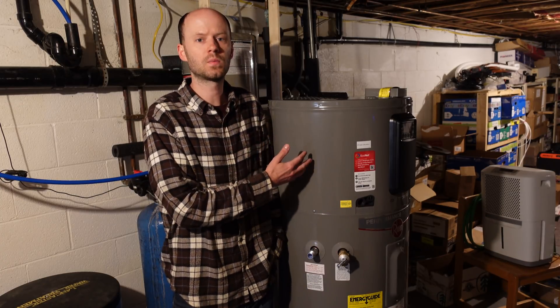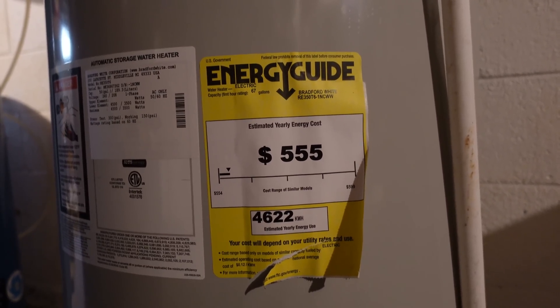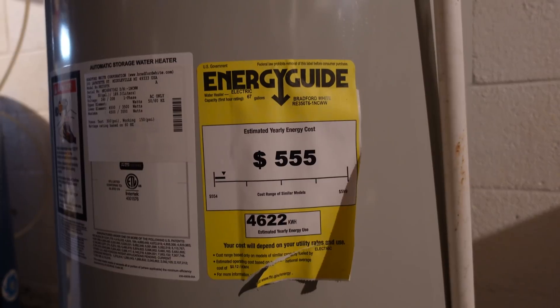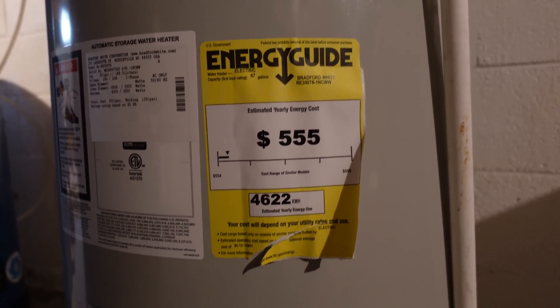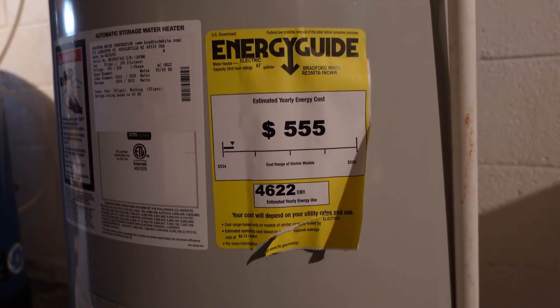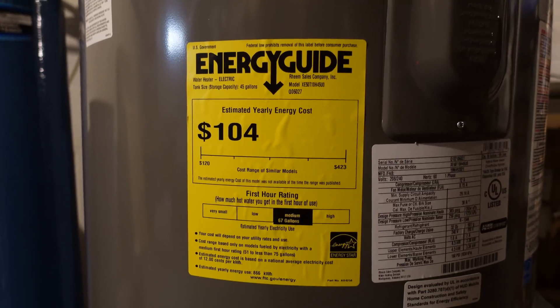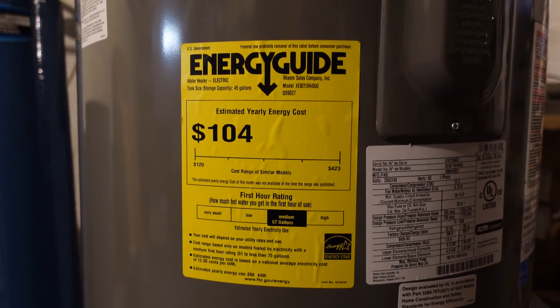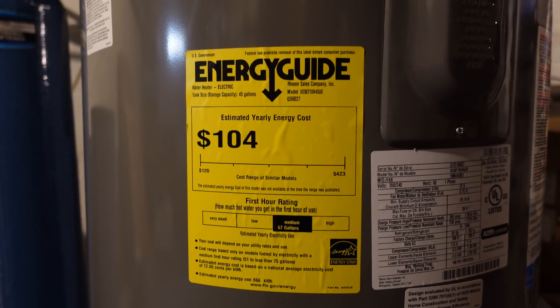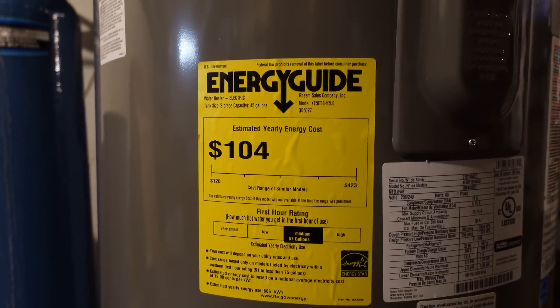The process of heating water this way is vastly more efficient. Looking at the Energy Guide label on the old water heater, it estimates $555 of power usage per year at 4,622 kilowatt-hours consumed. Going over to the new heater, the estimated annual cost is only $104. That is quite a big difference — and this is the same size tank, 50-gallon, with a 67-gallon first hour rating.